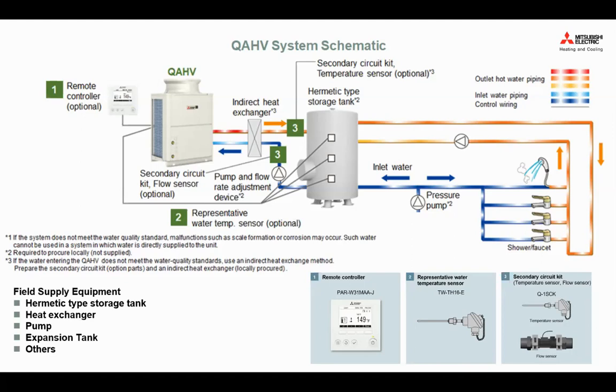So here it's just a very basic idea to introduce the concept for domestic hot water. You can see a basic schematic is usually, let's say, on the primary circuit, that means that's the QAHV circuit. It comes with the built-in internal pump to regulate the flow and then to meet the capacity, as well as the set water temperature. So let's imagine you have 15 degrees C of cold water going into the QAHV, and then you are creating, let's say, 70 degrees of hot water coming out on the left-hand side of the heat exchanger.